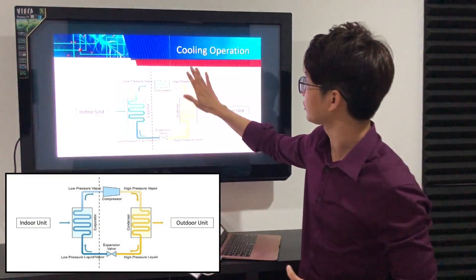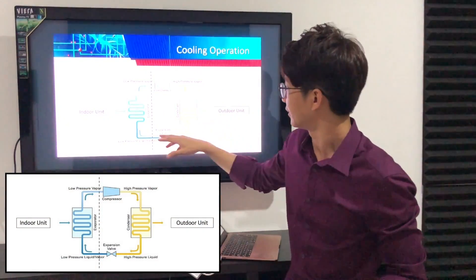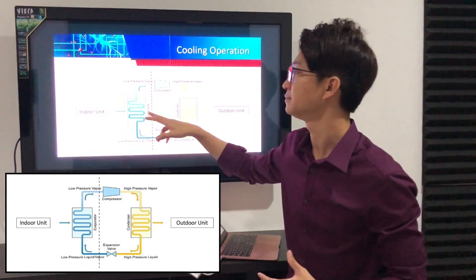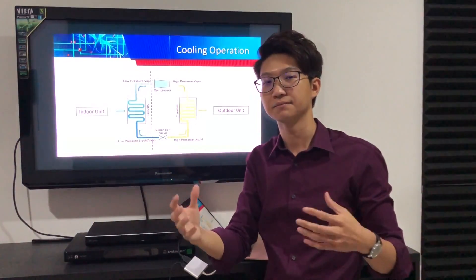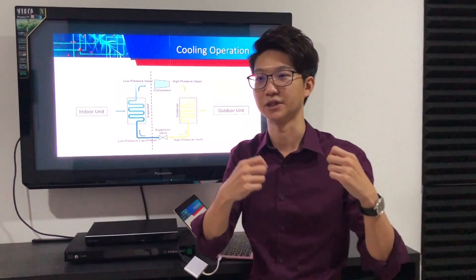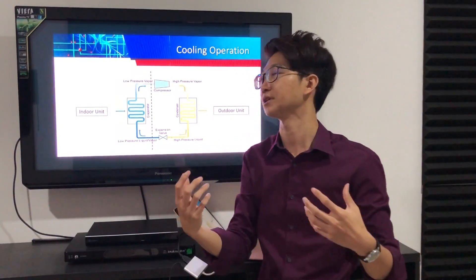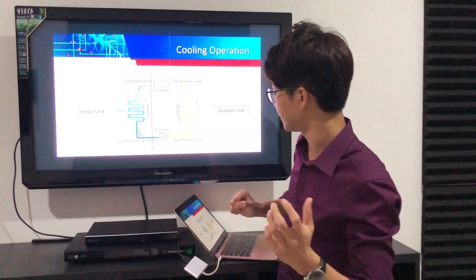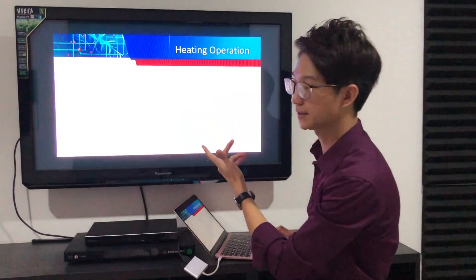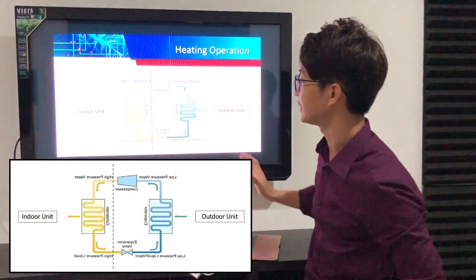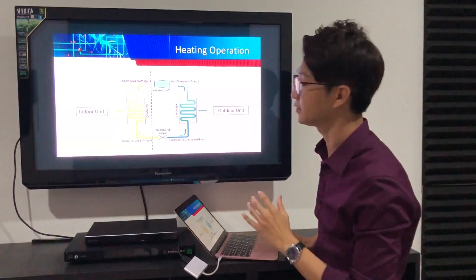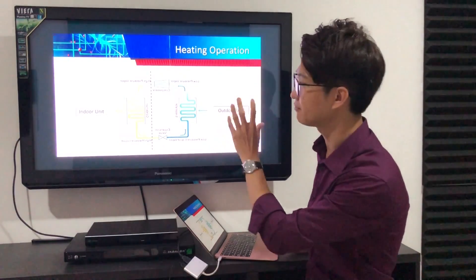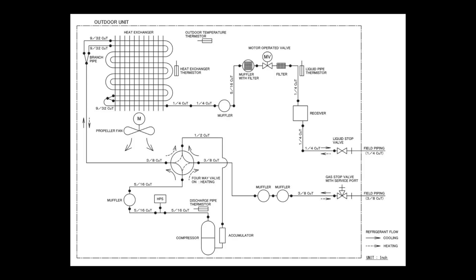Now, we are talking about cooling operation — we call the indoor unit the evaporator and the outdoor unit the condenser because we are referring to cooling mode. For heating, the mini-split heat pump version works differently. During heating operation, we simply flip the entire system — the indoor unit becomes the condenser and the outdoor unit becomes the evaporator. Here is a schematic diagram of the outdoor unit of a typical split air conditioner, which includes the necessary valves for heating.